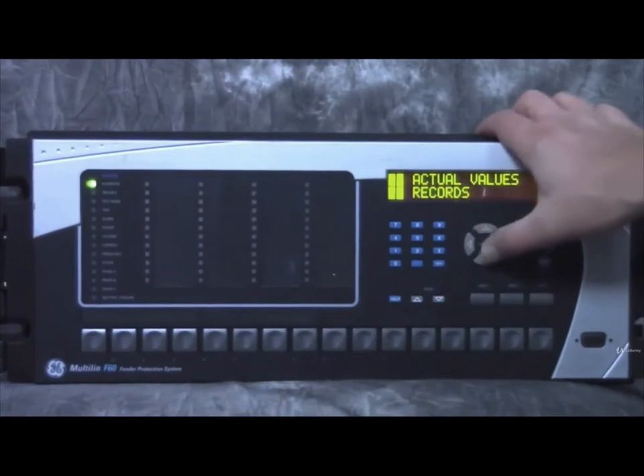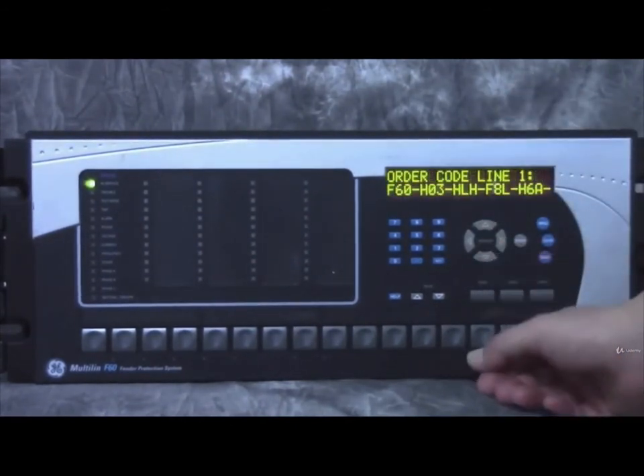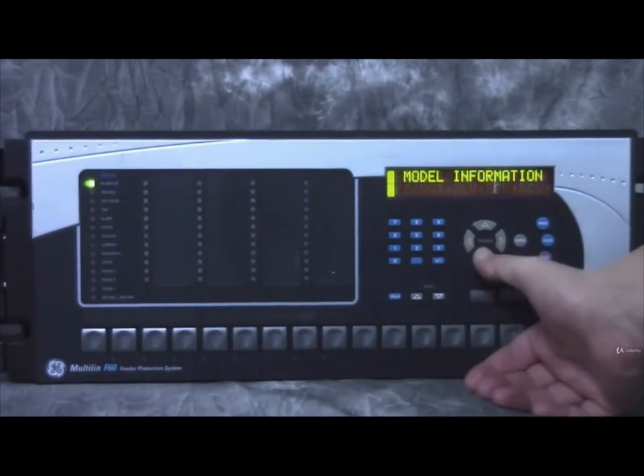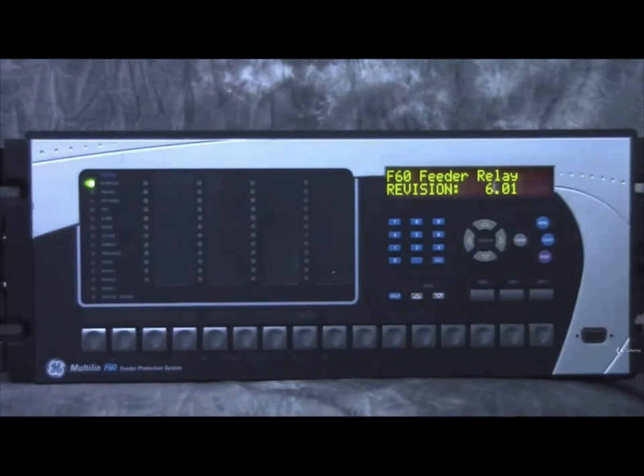In distribution applications, the replacement by the digital relay proceeded a bit more slowly. While a great majority of the feeder relays in new applications today are digital, the solid-state relay still sees some use where simplicity of application allows for simpler relays, which allows one to avoid the complexity of digital relays. The progress and enhancement of these relay changes happens continually, and as such, the following examples have already been improved and additions made. However, the basics are still there, and even though newer versions are available, these examples will give a good idea of what is out there and what has happened in the way of IEDs for transformer protection today.